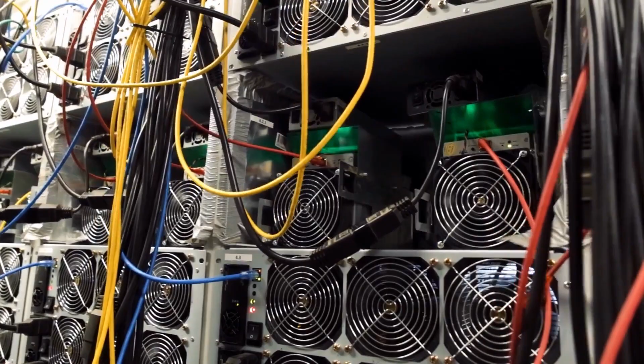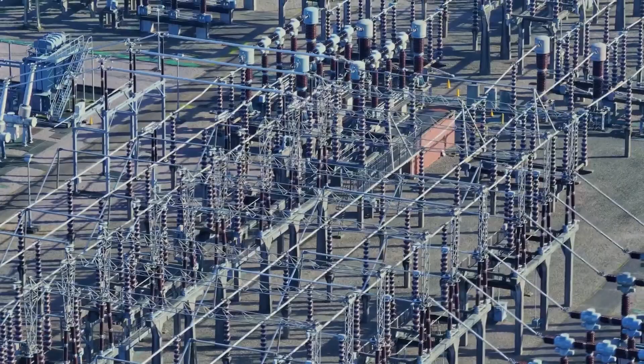So, how do you actually push electricity at a voltage nearly 40% higher than anything else running commercially on Earth without the whole system arcing apart? The honest answer is that going from 800 kilovolts to 1,100 kilovolts isn't a small step up. Engineers who've worked on these projects describe it as a far bigger technical leap than going from 500 to 800 kilovolts, because insulation requirements don't scale in a straight line with voltage, they scale exponentially. Every piece of equipment along the route, insulators, transformers, the massive converter stations at each end, has to be re-engineered from the ground up rather than simply built bigger.